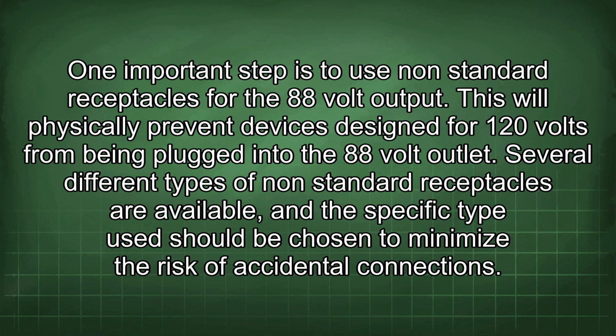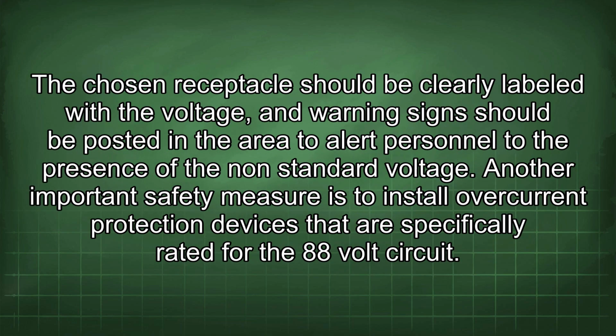One important step is to use non-standard receptacles for the 88-volt output. This will physically prevent devices designed for 120 volts from being plugged into the 88-volt outlet. Several different types of non-standard receptacles are available, and the specific type used should be chosen to minimize the risk of accidental connections. The chosen receptacle should be clearly labeled with the voltage, and warning signs should be posted in the area to alert personnel to the presence of the non-standard voltage.